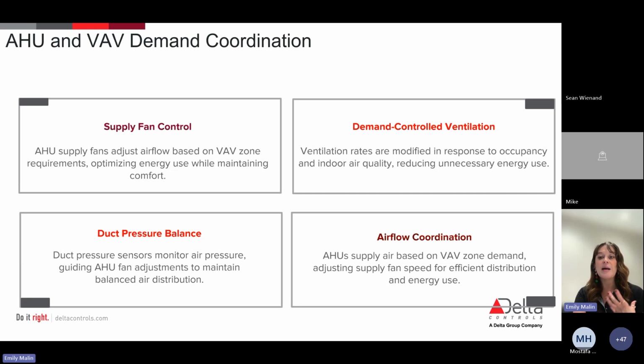The way that all of this is happening is basically with the air handling unit supply fan and the demand control ventilation; it's going to bring those two things together. Again, you're always getting your input from your duct pressure balance, but it's going to be a more precise and a more intelligent way to control those VAVs in order to match the occupancy use and still maintain your standards. We're going to talk a lot about this in Guideline 36, but what I wanted to do here is get you guys in that mentality of thinking through how all of these systems are going to be coordinated together to always work through our controlled loops. So this is what's going to happen in Guideline 36. Keep it in the back of your minds, but it's just another more intelligent way of controlling our VAVs with our air handling units.